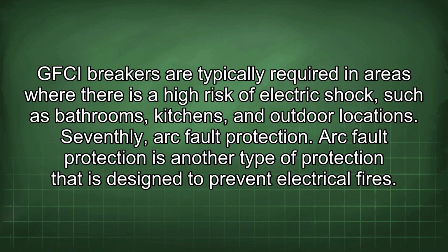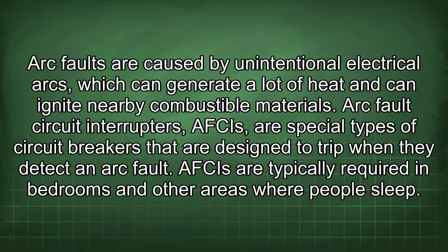Seventhly, arc fault protection. Arc fault protection is another type of protection that is designed to prevent electrical fires. Arc faults are caused by unintentional electrical arcs, which can generate a lot of heat and can ignite nearby combustible materials. Arc fault circuit interrupters, or AFCIs, are special types of circuit breakers that are designed to trip when they detect an arc fault. AFCIs are typically required in bedrooms and other areas where people sleep.